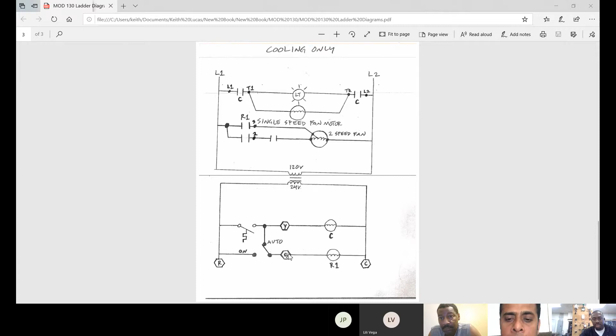So we're done with all the high voltage stuff. We have our L1 going to terminal 1, terminal 3 going to high speed, and neutral going to L2. We just did all of those things. This part right here would be for the heat, for low speed, but we're not going to pay any attention to that. All we got left now is our relay 1 coil, which needs to be connected to G and to common.